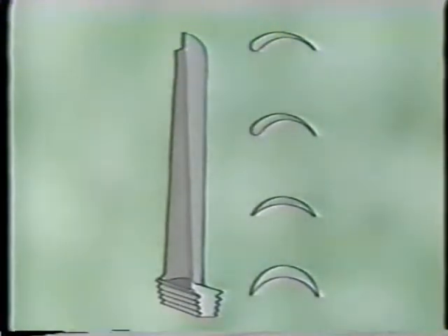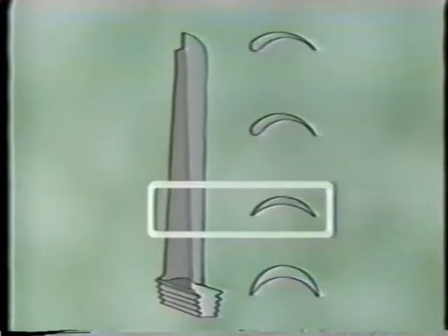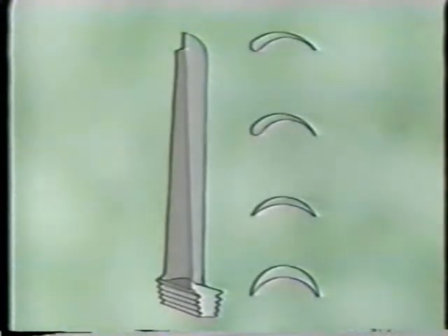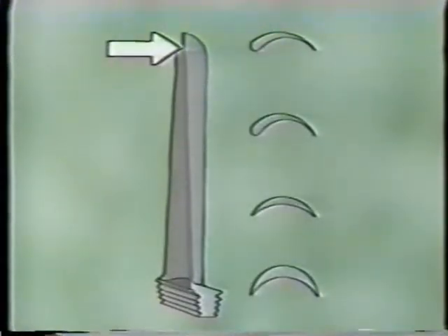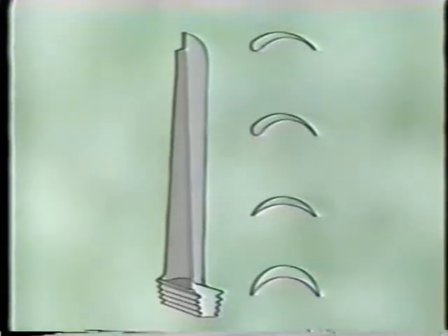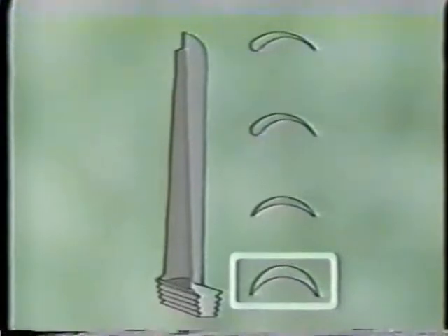Most turbine rotor blades today are completely impulse-shaped at the base and gradually change into a pure reaction shape at the tip. The reason for this change in blade shape is that the tip of the blade moves faster than the base because the tip has to cover a greater distance during each rotation. The streamlined reaction shape moves more smoothly at high speeds through the flowing gas than does the cup-like impulse shape.